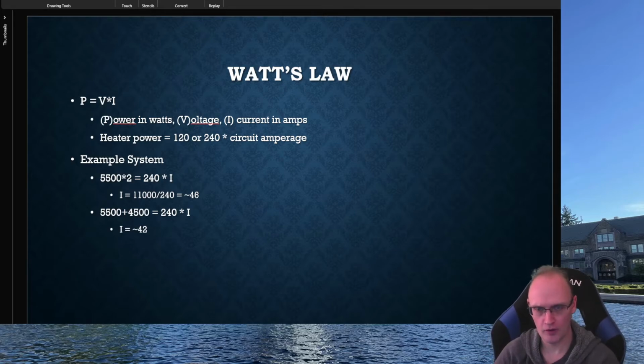And to put that in a little more practical terms, we can say heating power, the power consumed by our heating elements in watts, is equal to our circuit voltage, which is either going to be 120 or 240, depending on your circuit, times the amperage of that circuit. 30 amps, 50 amps, 20 amps. So the example that I'm going to use is my thought process in designing this part of my panel. So at first, I started out with 2 5,500 watt heating elements. And these are on a 240 volt circuit.